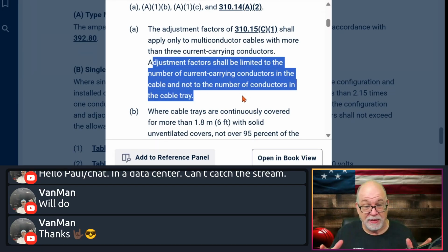That's important. If you're designing a system and you realize that I'm putting these cables in a cable tray, as long as I don't have more than 3 current carrying conductors in each cable, and I'm following the rules in the cable tray, because we've got rules in 392.22 that say how you space them and how you install them. If I follow those rules, then I don't have to worry about 310.15(C)(1). That's so important, these rules.